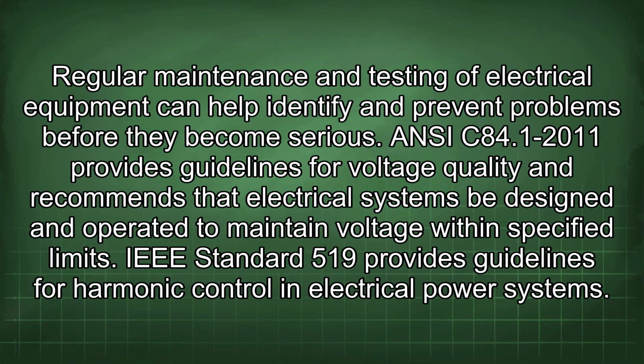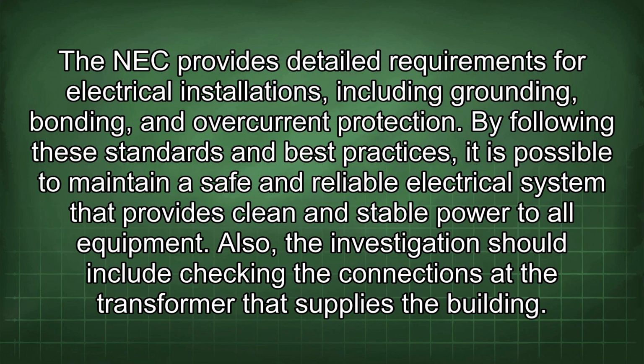ANSI C84.1-2011 provides guidelines for voltage quality and recommends that electrical systems be designed and operated to maintain voltage within specified limits. IEEE Standard 519 provides guidelines for harmonic control in electrical power systems. The NEC provides detailed requirements for electrical installations, including grounding, bonding, and overcurrent protection. By following these standards and best practices, it is possible to maintain a safe and reliable electrical system that provides clean and stable power to all equipment.